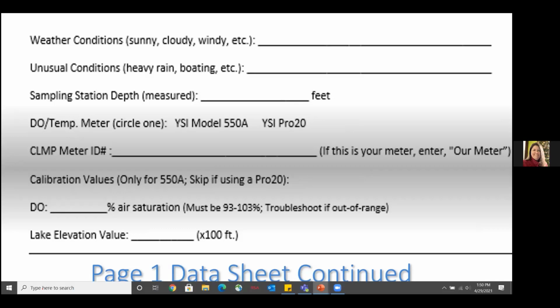And then we need the calibration values only if you're using the 550A. So the Pro 20 is able to determine the lake elevation based on barometric pressure. But the 550As don't have that. So you, with your kit, if you get a 550A, we'll give you what the lake elevation is. We find it online for you. But we want you to enter that in so that we know that you calibrated it and know the elevation for where you're at. And then also put in what the percent air saturation was when you calibrated.